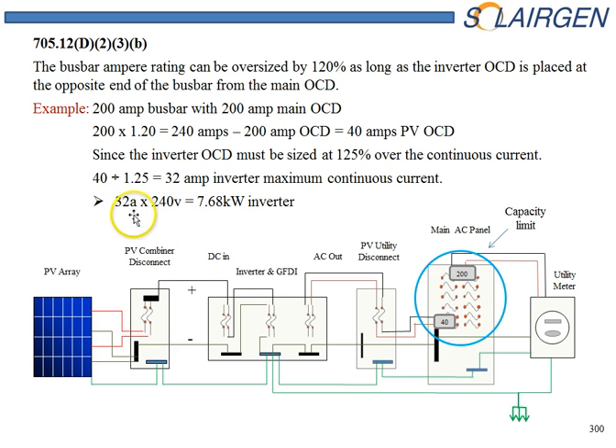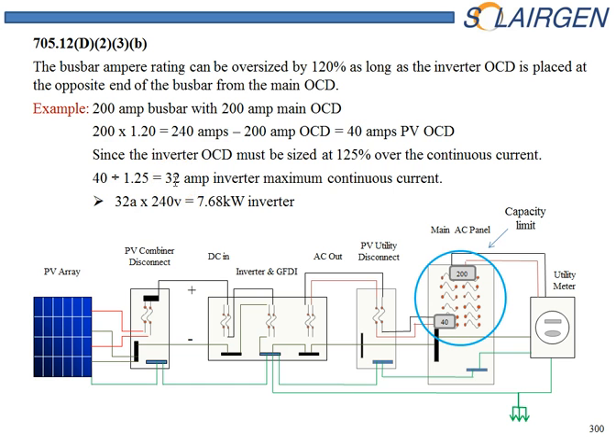When we determine how large of an inverter we can connect, we take that overcurrent device and divide by 125% to find the ampacity of the inverter. The reason we do that is because we have to size the overcurrent device 125% greater than the continuous current. So we're basically backing in to find out what the capacity of the inverter could be. That's option one for load side connections.